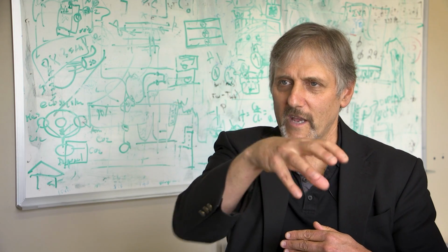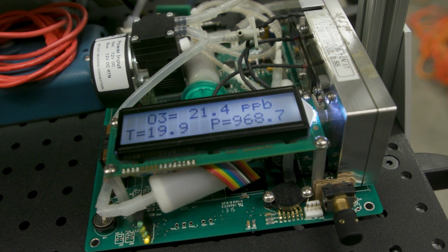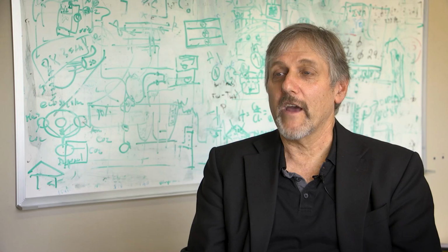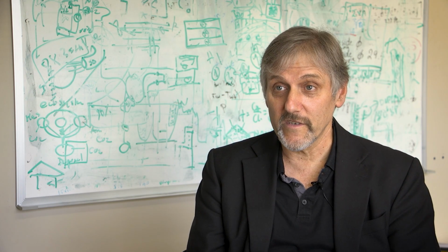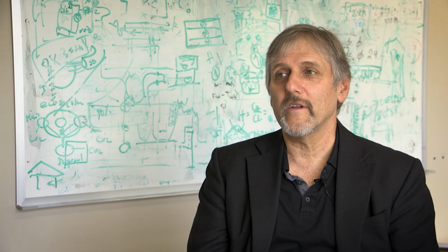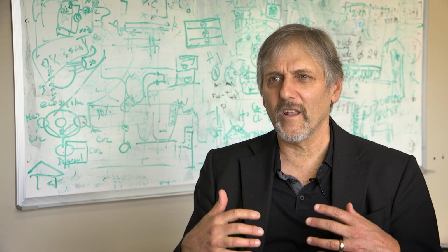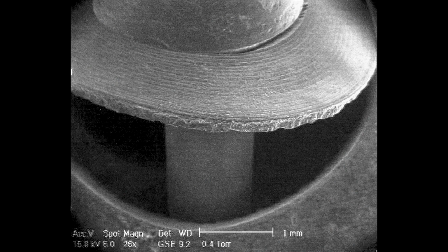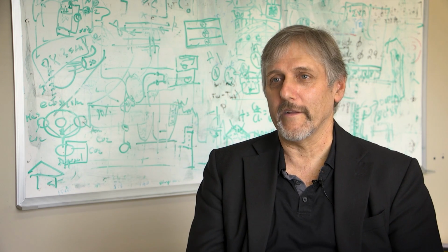Well, the company that came into his home set up, to my recollection, I believe 6 commercial-size ozone generators, switched them all on full blast, and forgot to tell the family they shouldn't be in the house when these things were switched on. The person had a 3-year-old daughter, a dog, a wife, and himself, who all became sick. It also harmed a lot of works of art. It degraded a lot of rubber in the house, rubber gaskets. They had leaky water heaters because of ozone reacting with rubber. So it really damaged the house, in my opinion, permanently.